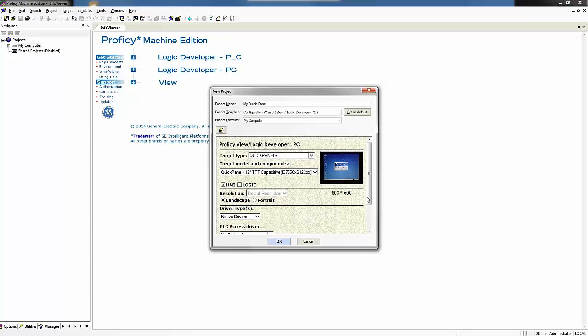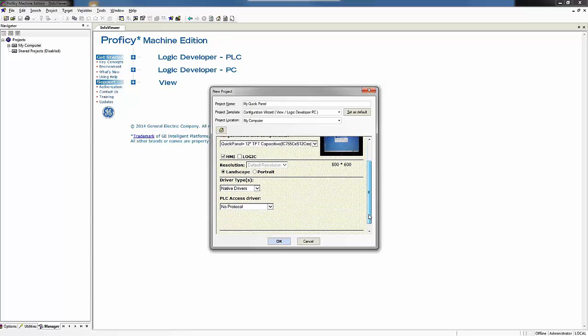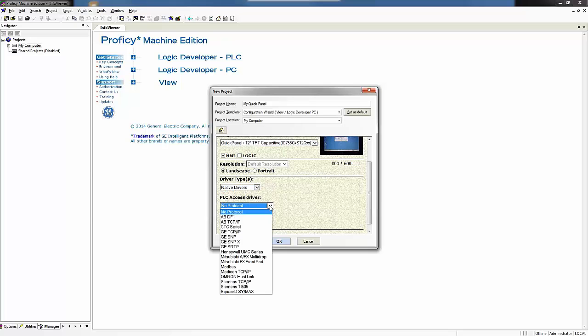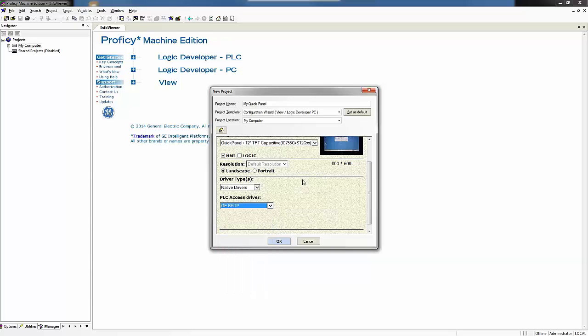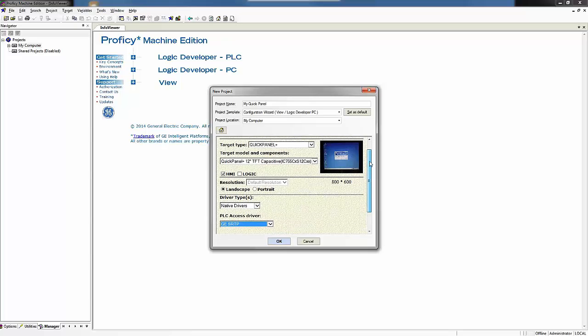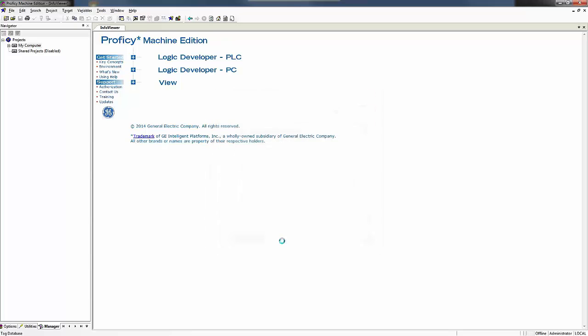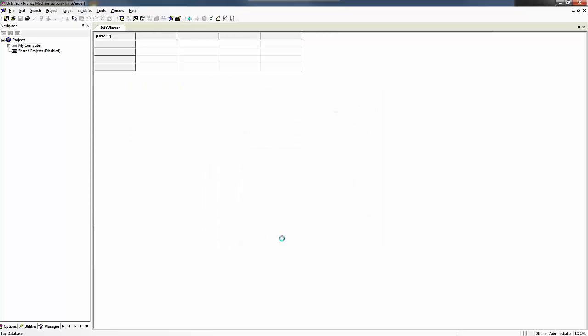And I'm going to be connecting it today to a GE RX3i controller. So I can choose a native driver. And the protocol for the GE over ethernet is the GE SRTP protocol. So this will allow me to set my target up very rapidly for my QuickPanel. So I'm going to hit OK here and watch my target be built with the proper components.